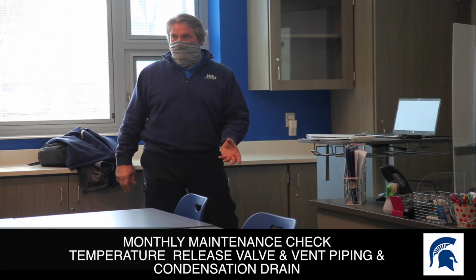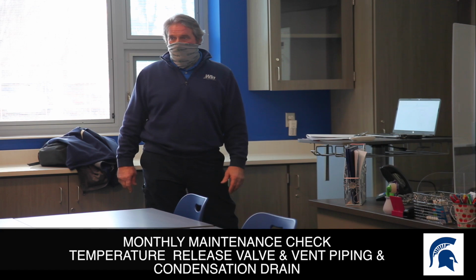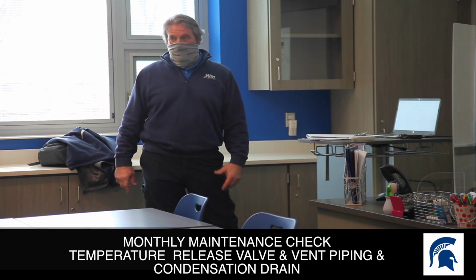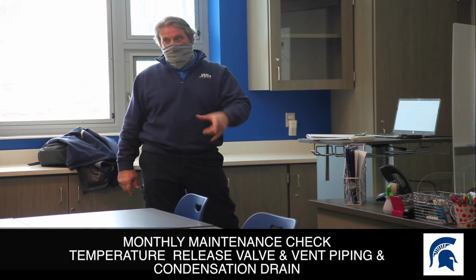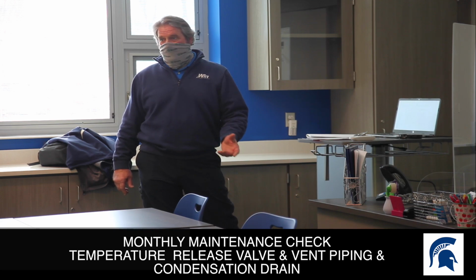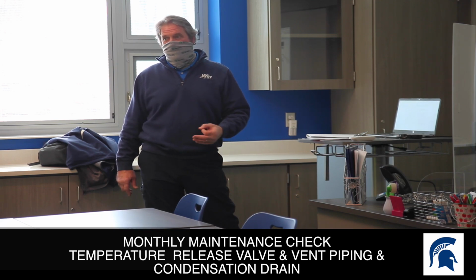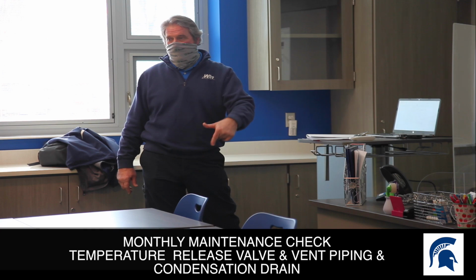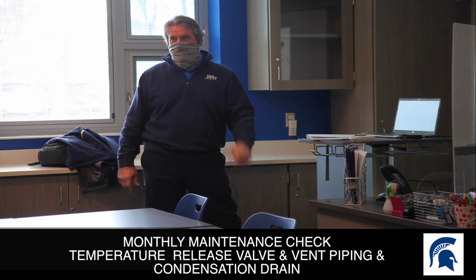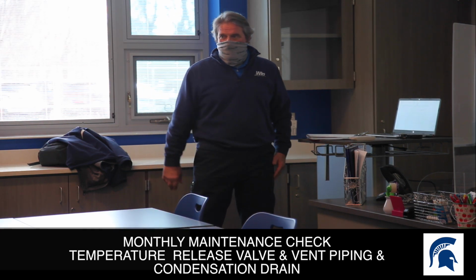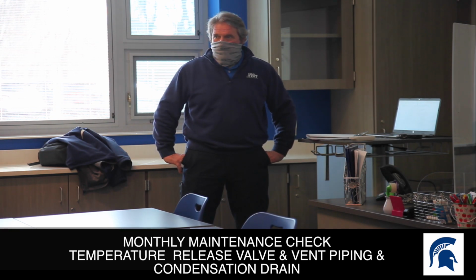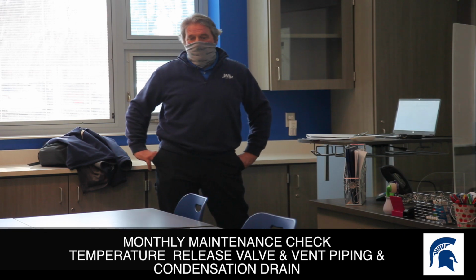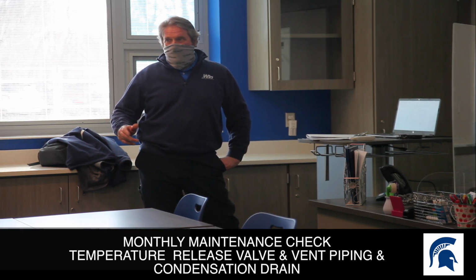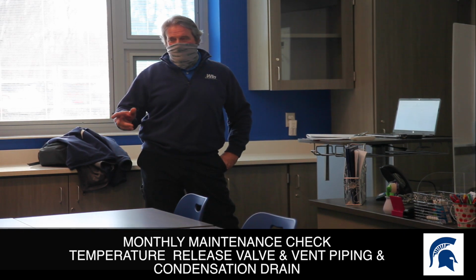So when the pipe goes out by the drain, there should always be just a little constant drip, condensate. Oh, absolutely. When that heater's fired up, there should always be condensate. If you don't have condensation, then you have a problem. It's either in the trap or the neutralizing kit's getting backed up. Is there a drain at the back of the hot water tank to open it up like your water tank at home, like a domestic hot water tank? No. Get the sludge out of it? No, because that's a closed system.